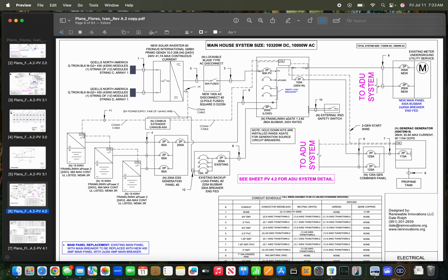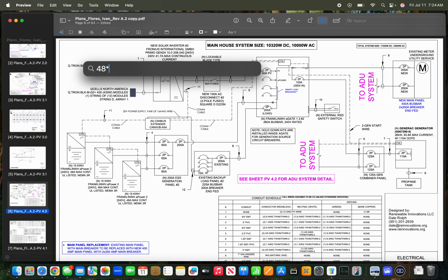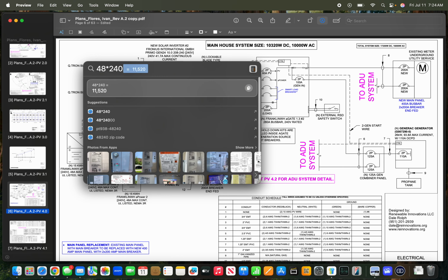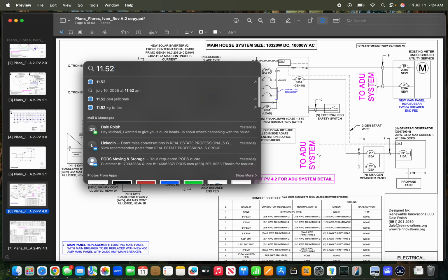The main house has 3 batteries: three 15 kilowatt hour batteries, each capable of 48 amps max continuous power output, so we're looking at 180 amps of power surge capabilities. The surge is actually misspoken there; these things can surge pretty high, but at 48 amps continuously at 240 volts, we're looking at 11.52 kilowatts of power each.